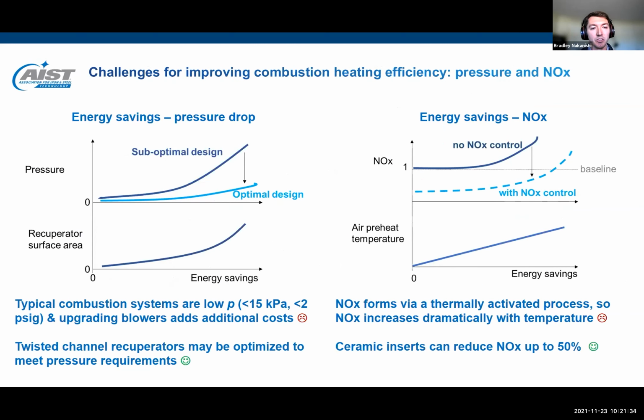The two main challenges for improving efficiency of recuperated combustion heating systems are pressure and NOx. Here, I schematically show how pressure, that is the pressure drop between the air blower and exhaust, recuperator surface area, NOx emissions, and preheat air temperature vary with energy savings. Focusing on the left, you see how recuperator surface area and pressure both increase as energy savings increases. Typical blowers operate at low pressure, and system upgrades add additional costs.